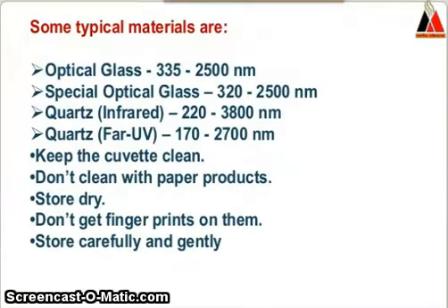So some typical materials are: optical glass 335 to 2500 nanometer, special optical glass 320 to 2500 nanometer, quartz infrared 220 to 3800 nanometer, quartz far UV 170 to 2700 nanometer. Keep the cuvette clean, don't clean with paper products, store dry, don't get fingerprints on them, store carefully and gently.